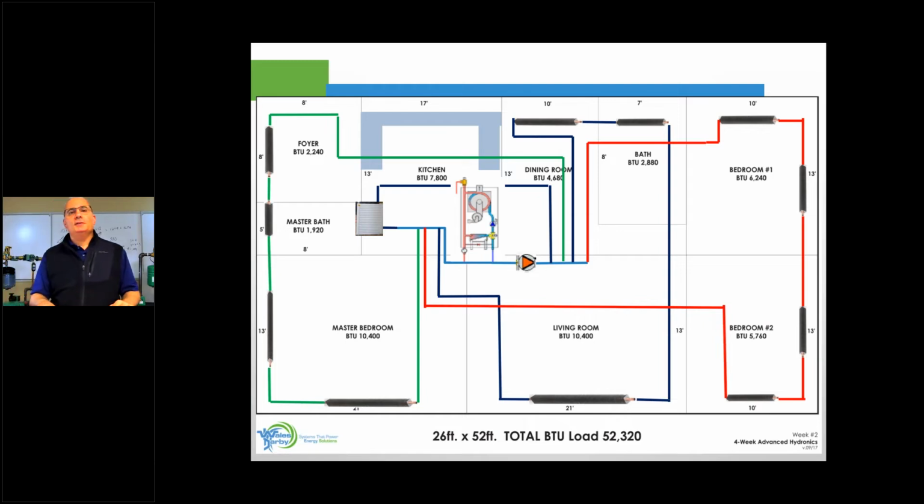What if we made it a 50-foot loop? No calculator needed. It'll be 3 feet. What if we cut 50 feet in half and make it 25? No calculator needed. It's now 1.5. So if I know those 3 numbers, what if I go now to 125? Well, if 100 was 6 and 25 was 1.5, it's 7.5. 150 should be 9. 175 should be 10.5. And 200 would be 12.